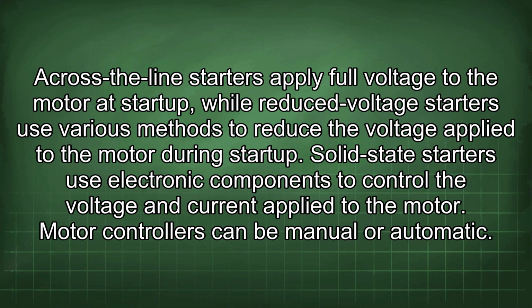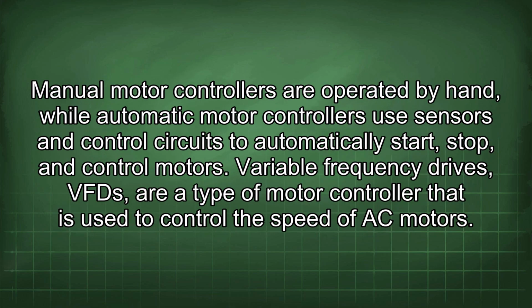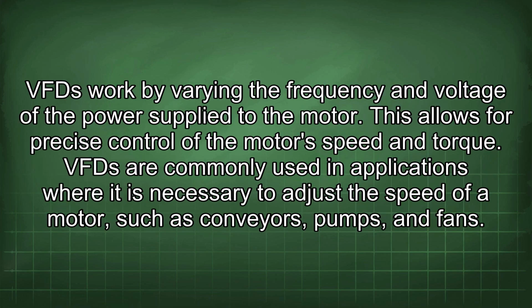Motor controllers can be manual or automatic. Manual motor controllers are operated by hand, while automatic motor controllers use sensors and control circuits to automatically start, stop, and control motors. Variable frequency drives, VFDs, are a type of motor controller that is used to control the speed of AC motors. VFDs work by varying the frequency and voltage of the power supplied to the motor. This allows for precise control of the motor's speed and torque. VFDs are commonly used in applications where it is necessary to adjust the speed of a motor, such as conveyors, pumps, and fans.